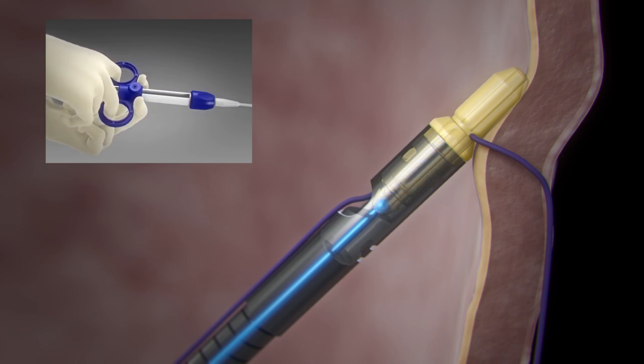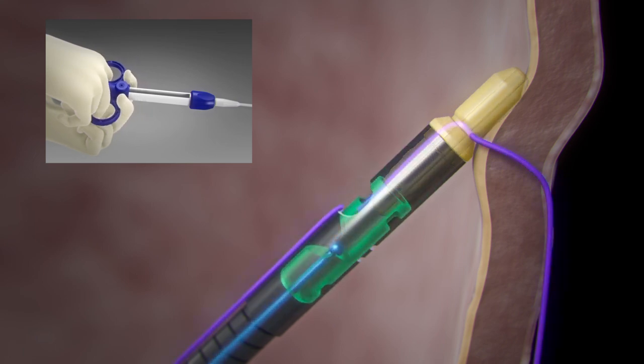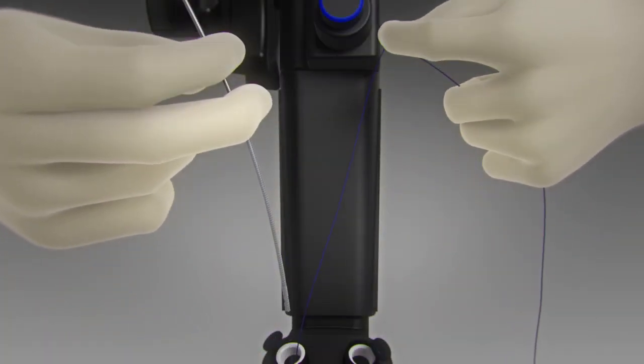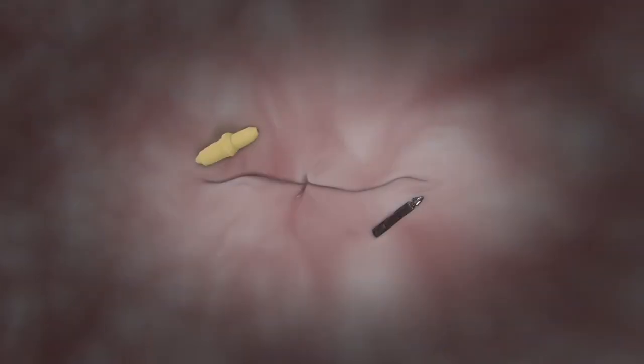Finally, continue to squeeze the handle to activate the suture cutter and release the PEEK collar and plug. Remove the cinch and suture from the scope channel.